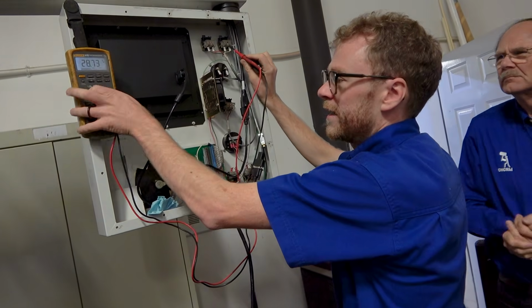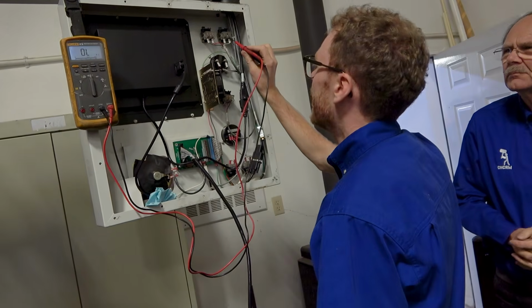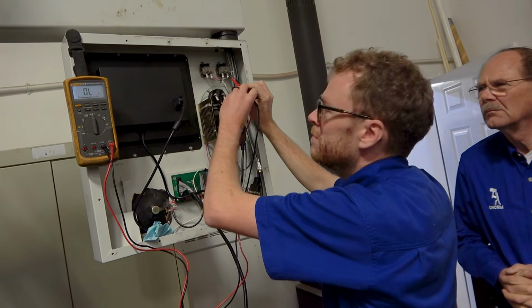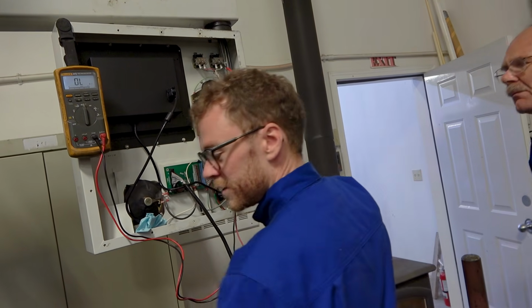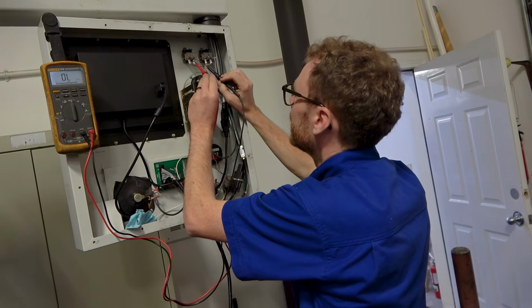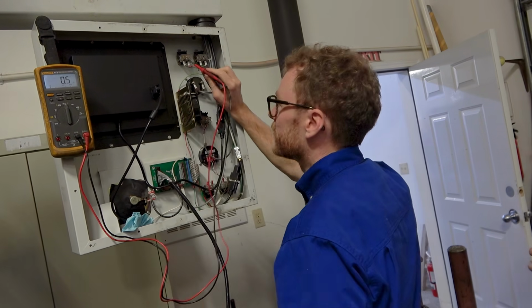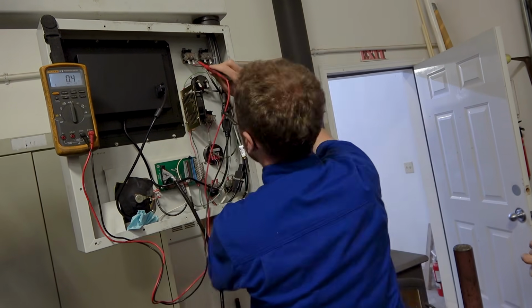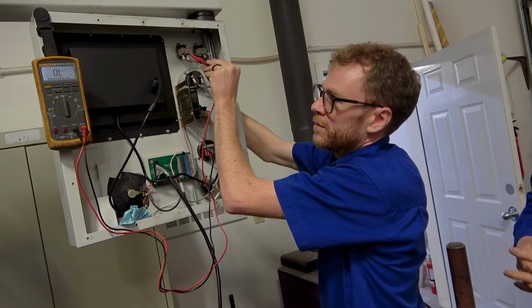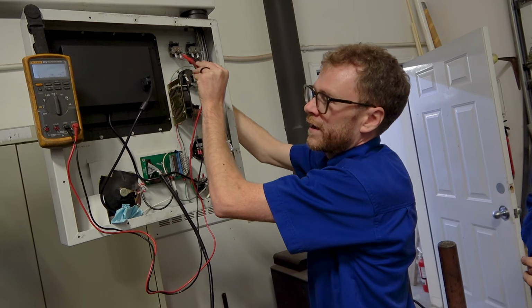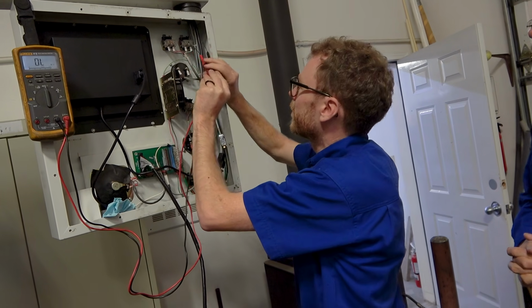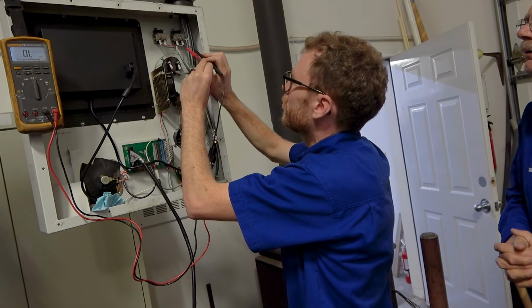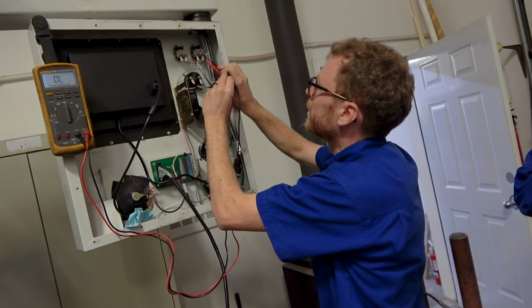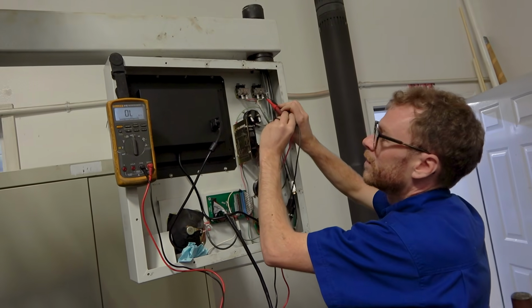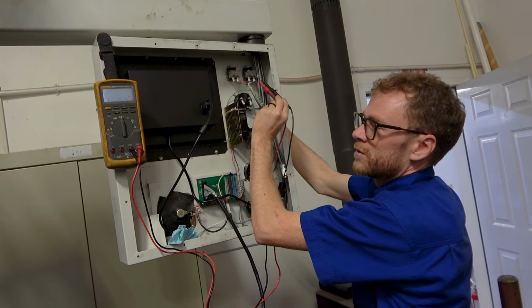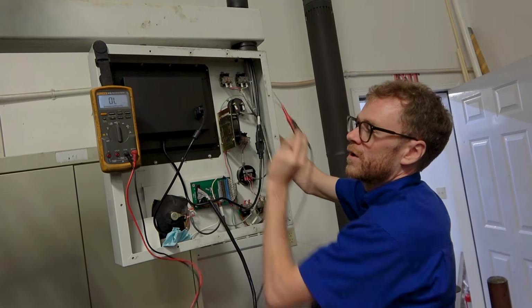Now let's just for kicks check resistance. That one's open, which according to this is an open switch - so that reads good. Let's read this one - it reads closed, and if I push it, it should change to open. Now if we check this other one, which is normally open, if I push the button in, it should change resistance and measure zero.